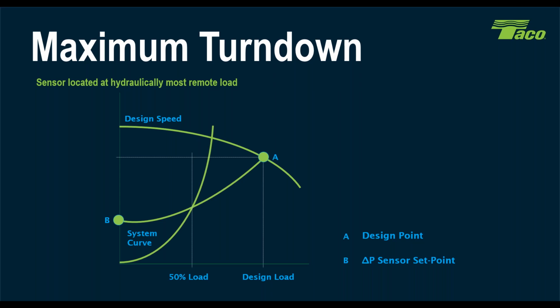Now at 50% load, you can see that we end up with a much greater turn down. So now at 50% load, our speed is down to probably 35 or 40% of design maximum speed. So there's a much greater energy savings the further away we get that sensor. And the problem is that in a lot of specifications, one of the things I see all the time is engineers say, oh, I'll put it 2/3 out the longest pipe run. Well, is that really the right place for it?